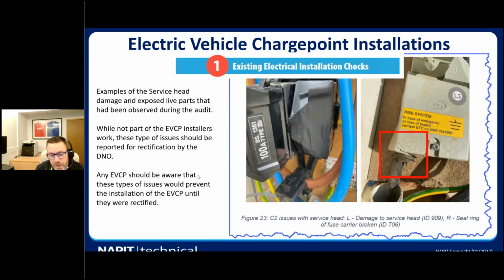We did have some examples of service heads which were damaged or exposed live parts that were observed during the audits. And while this does not form part of the EV installer's work, these issues should be reported for rectification by the DNO, and that is issued to the client to get the issues corrected. A couple of these examples are damaged service heads. So this one here, we've got tape over the neutral connections, damaged cracked units to the edge of the service cutout. These are all things that should be highlighted and put forward to the client to get rectified by the DNO or supplier.